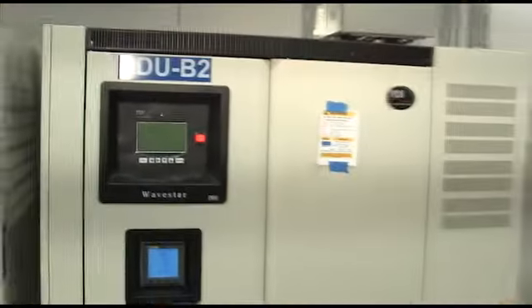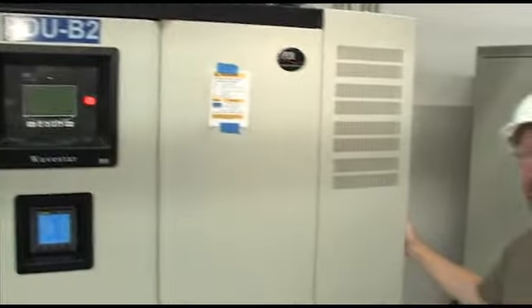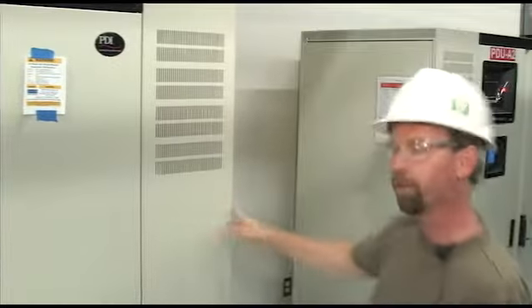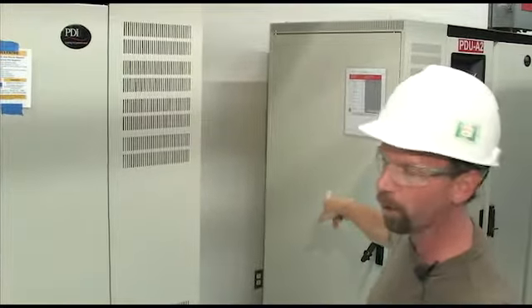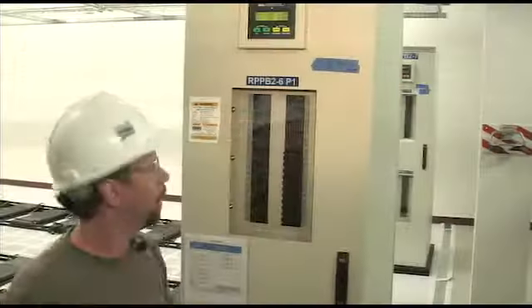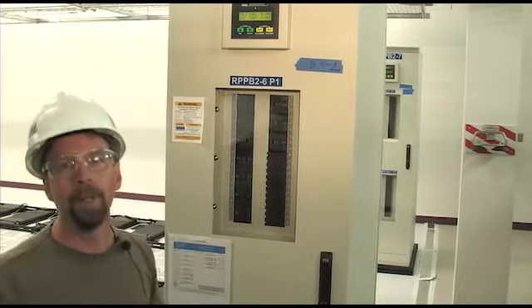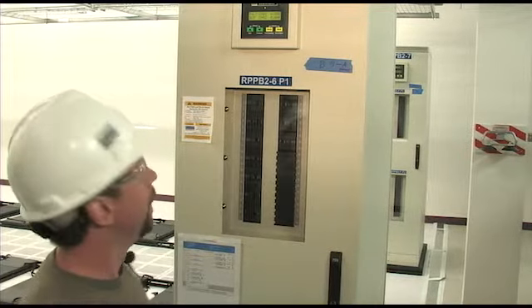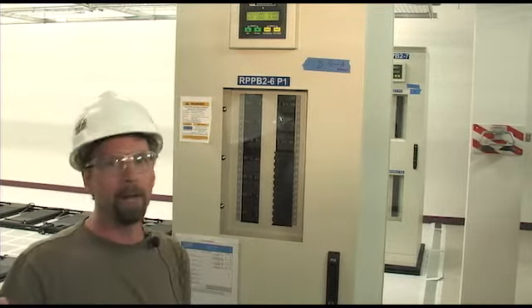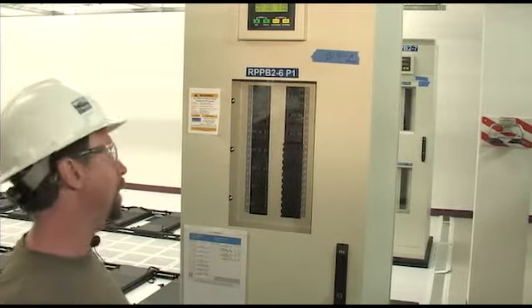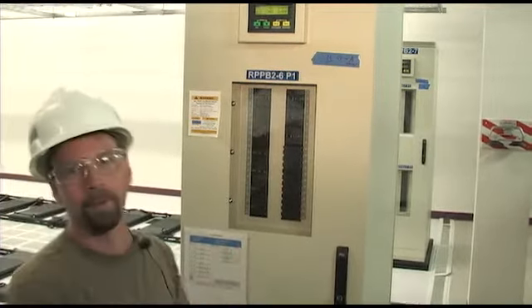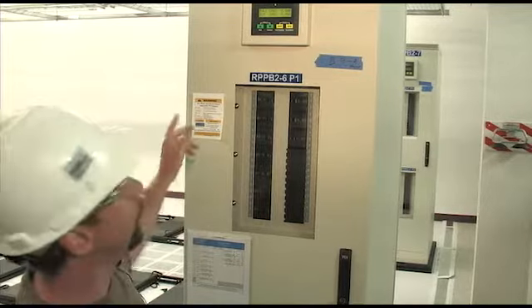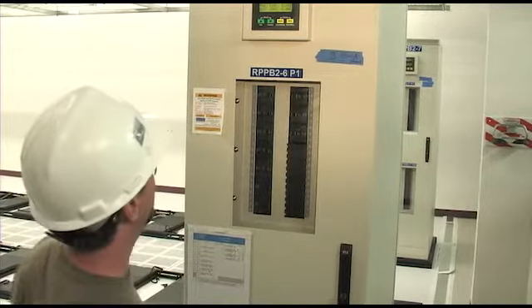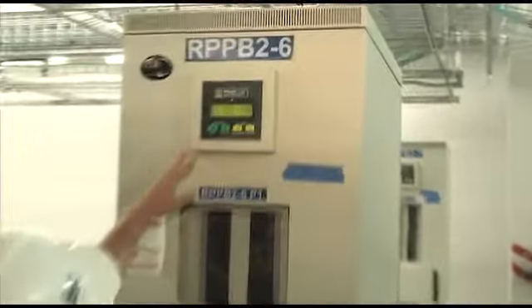So in this case, the breakers that distribute out to the RPPs are right here. I kind of showed them to you on this one so you can see what they were. Now we're going to go over to the RPP and take a look at one of those. This is the RPP, which is a remote power panel. Each breaker that was on the side of the PDU is distributing, each breaker is going out to one of these. This is one of them. This has an individual branch circuit monitoring. It has a simple display here.